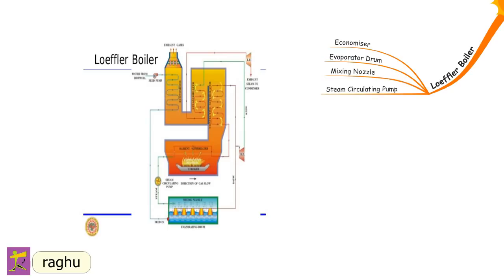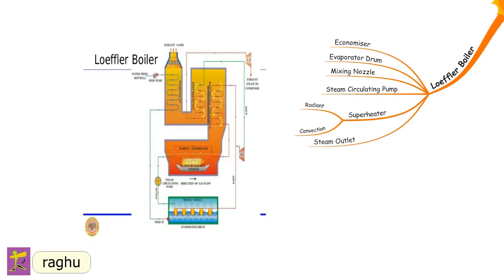The steam circulating pump forces steam from the evaporator drum to the radiant superheater. The radiant superheater, placed in the furnace, uses hot furnace gases to superheat the saturated steam from the drum. Steam from the radiant superheater then enters the convection superheater, where it is finally heated to 500°C. Both radiant and convection superheaters are arranged in series in the path of flue gases. One-third of the superheated steam from the convection superheater passes to the steam turbine, and the remaining two-thirds is passed back to the evaporator drum.